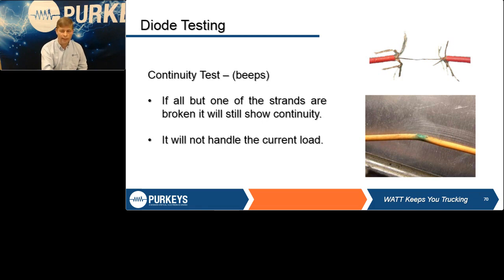But the exact same thing can happen if you have a wire that somebody stabs with a test light and you start getting corrosion in there. The end result is still the same thing: you cannot pass any current through that wire, but it will show continuity. So continuity can be a very handy thing, but it can also get you in trouble.